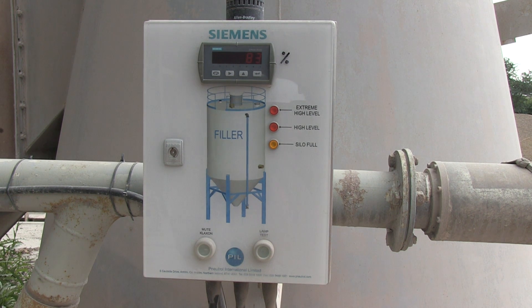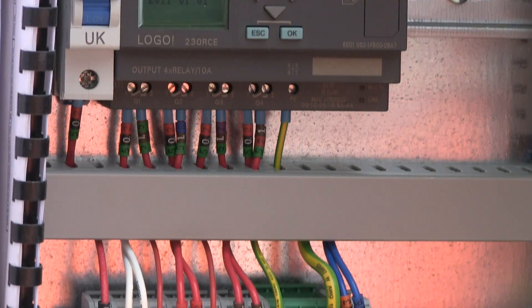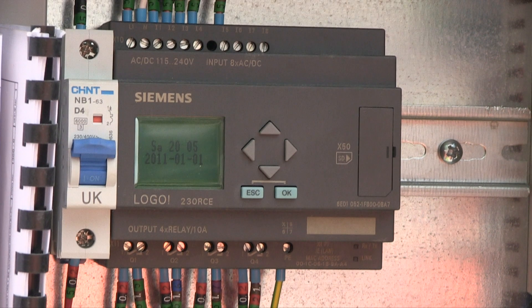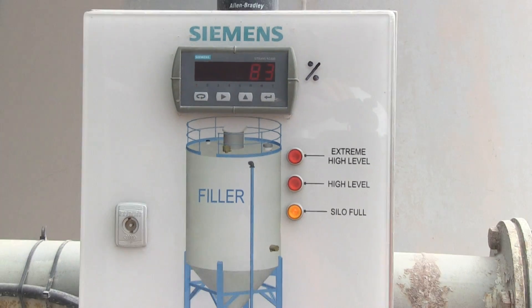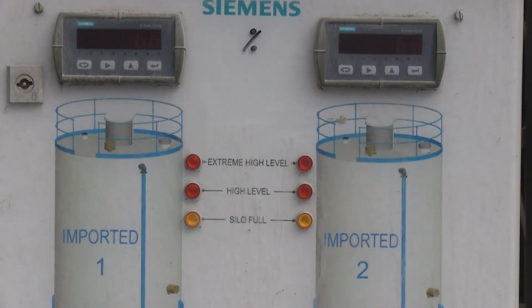The two level transmitters are connected to a panel at the bottom of the silo. Inside the panel, there is a Siemens Logo Small Scale Automation Logic Controller. The Logo integrates the signals from the level devices, displays the level reading on the Sitrans RD200 display, and controls the alarm indicators on the front of the panel. The delivery driver can now see how much material is in the silo when they arrive.